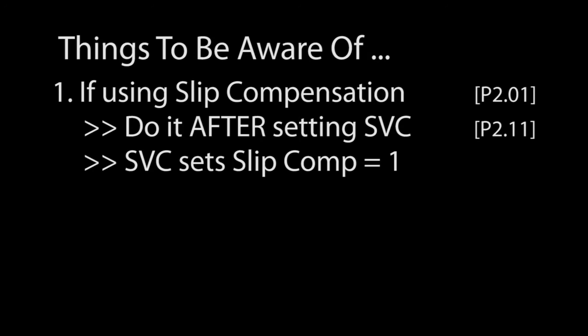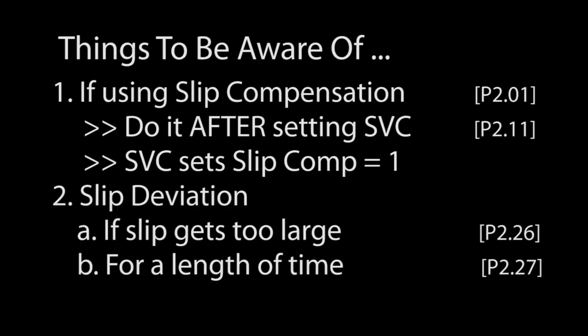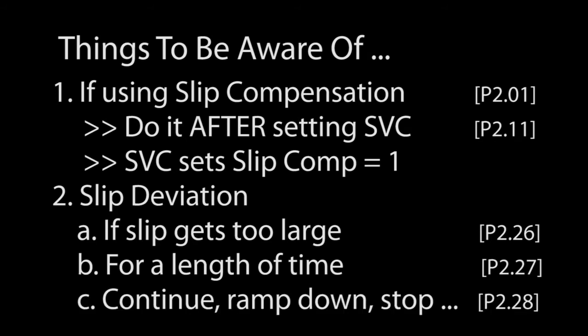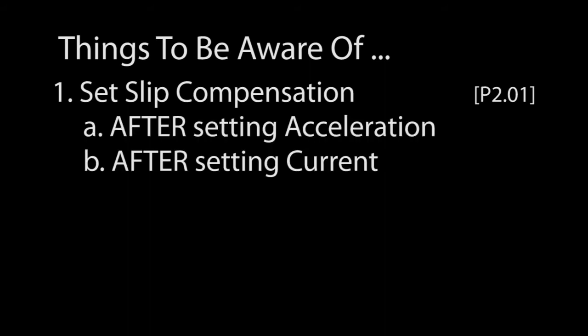If you are using slip compensation, you can also specify that if the slip deviates and gets too large for a certain amount of time, what the drive should do — that's a nice feature. Remember to set the slip compensation after setting the acceleration and current parameters. Slip is a function of torque, and torque is usually greatest during acceleration, which is also when you will be most likely to hit the current overload, so it's important to set those before tweaking the compensation.